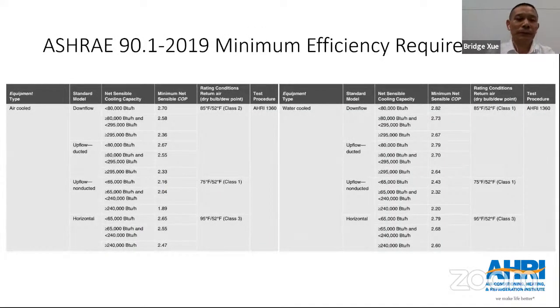So you can see here, they have different energy efficiency requirements for air cooled, water chiller, and water cooled equipment. They also have different configurations: downflow, upflow, ducted, without ducted, and horizontal unit. So when you make the selections for your data center, you need to make sure which efficiency you are talking about. You can decide, so the minimum sensible efficiency will be applied, either for an air cooled unit or maybe a water cooled unit. They have two main types of unit.